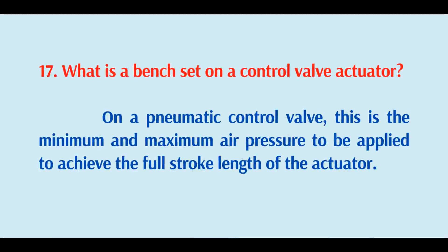What is a bench set on a control valve actuator? On a pneumatic control valve, this is the minimum and maximum air pressure to be applied to achieve the full stroke length of the actuator.